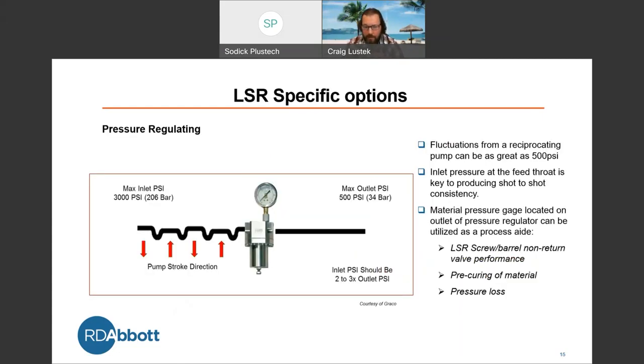The pressure regulation, again, this is where we want to isolate those pump strokes. So in the direction of your pump stroke, you have high and low pressures. We want those fluctuations to be flat. We want our inlet pressure to be a nice smooth flow. This allows us to get a consistent fill. And again, looking at this, with this regulator and the gauge, it shows us the performance of our non-return valve.